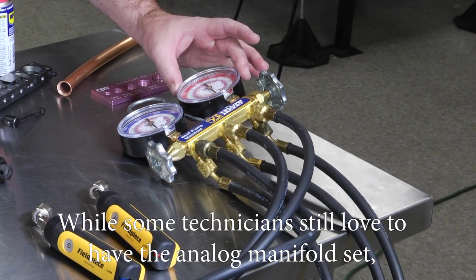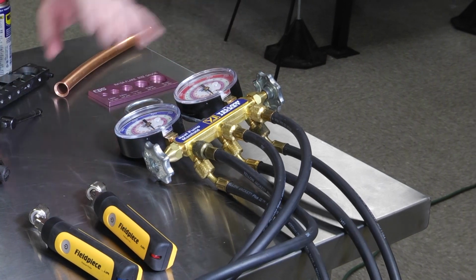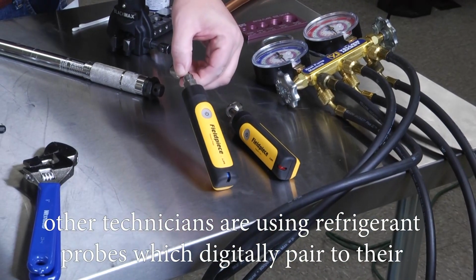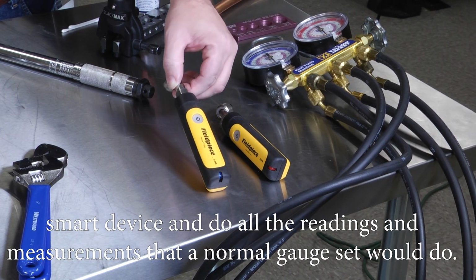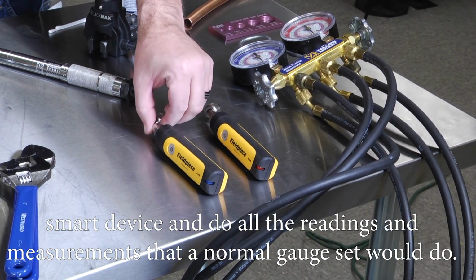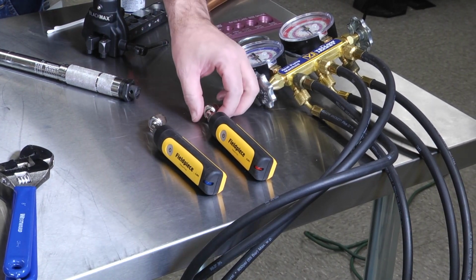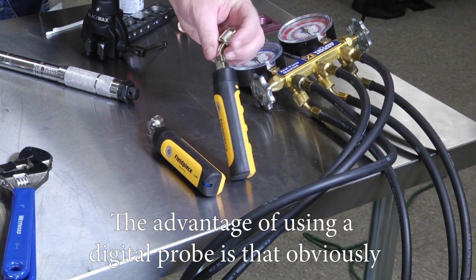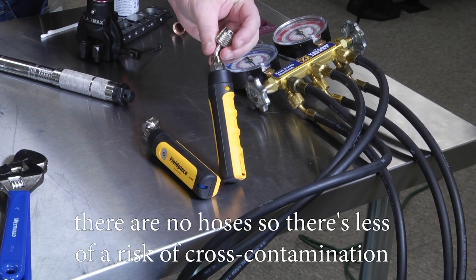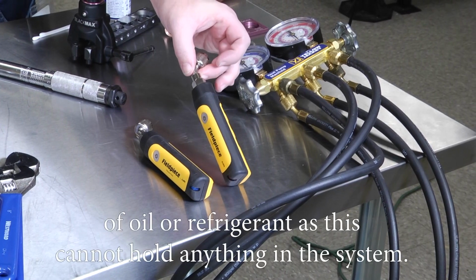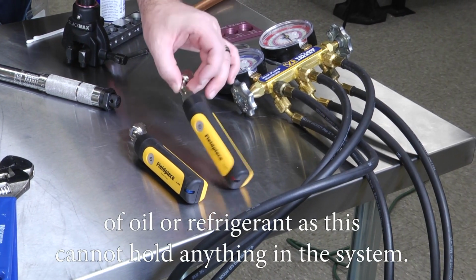Now, while some technicians still love to have the analog manifold set, other technicians are using refrigerant probes, which digitally pair to their smart device and do all the readings and measurements that a normal gauge set would do. The advantage of using a digital probe is obviously there's no hoses, so there's less of a risk of cross-contamination of oil or refrigerant, as this cannot hold anything in the system.